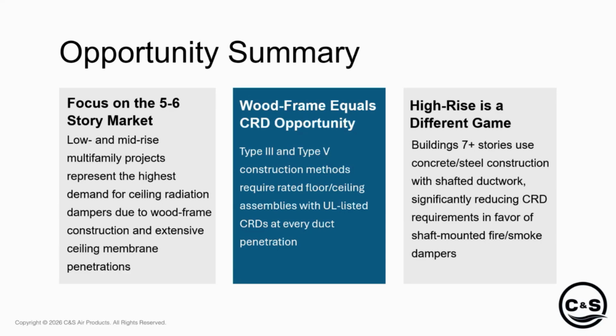So pretty much every ceiling radiation damper out there on the market is designed and tested with a static system. So there's no airflow moving through the system. It makes it very easy to contain the heat load and make sure that things aren't collapsing earlier than they are designed to. So this goes back probably 10 or 15 years, but UL designed a test, 15 years ago, to say, okay, we want to design a dynamic ceiling radiation damper so people can have that application out there.